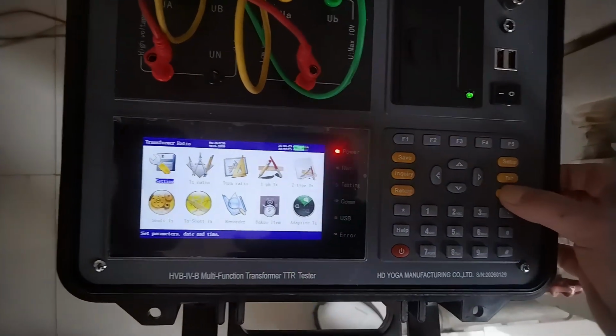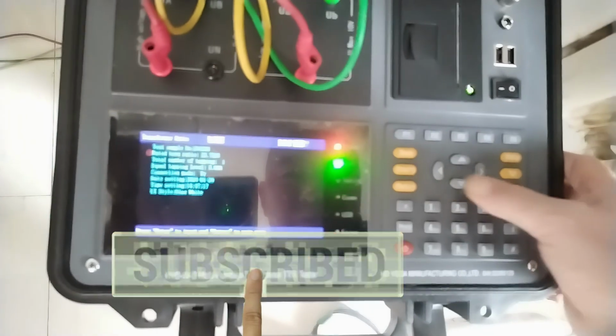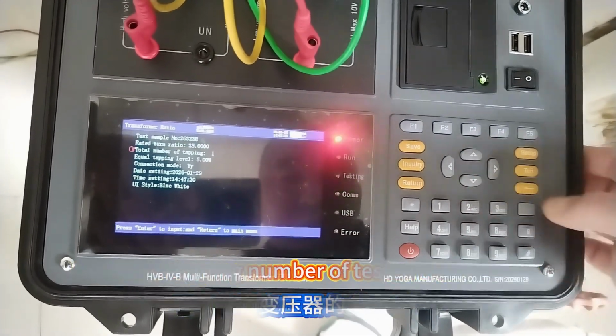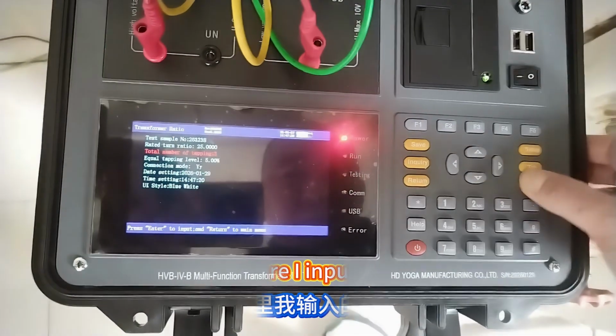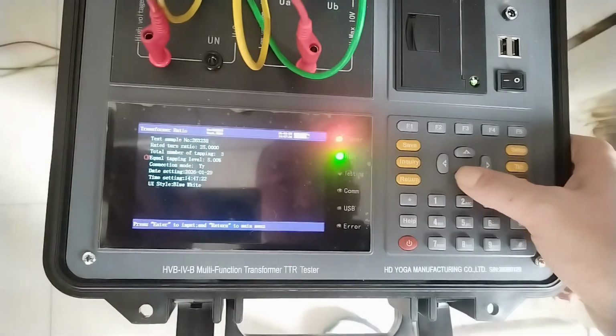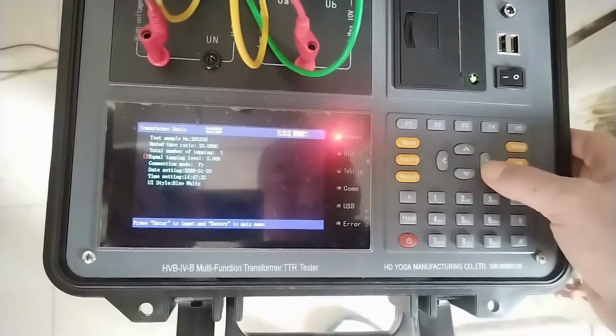Press the Enter key and input the rated turns ratio of the tested transformer. Here I input 25. Input the tapping number of the tested transformer. Here I input 3, equal tap levels. Our 10 kV transformer tap changer has 3 positions, each adjustment changes 500 volts, so we'll fill in 5% here.